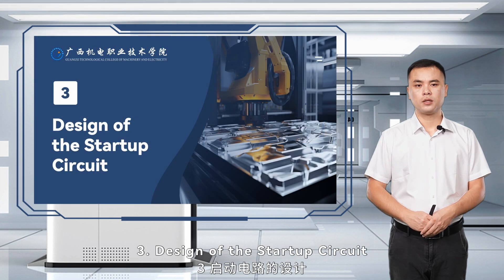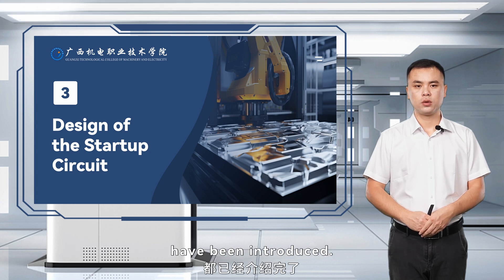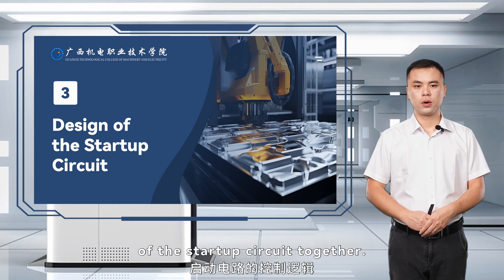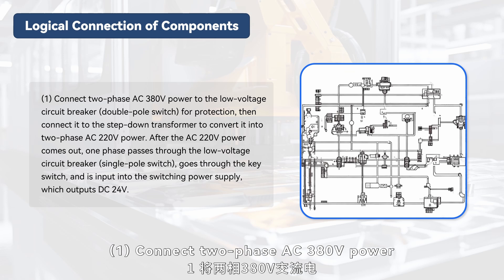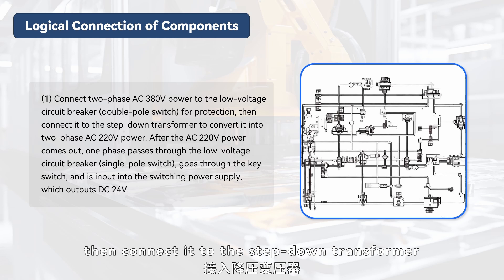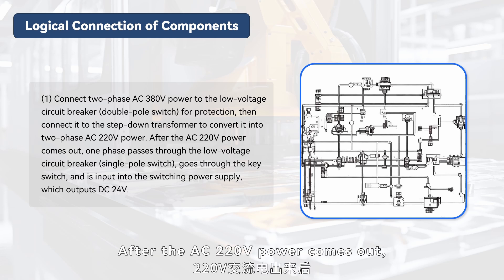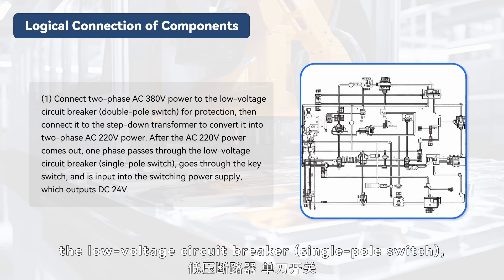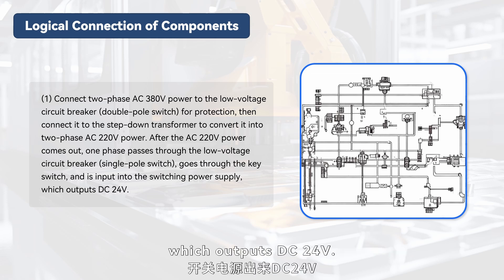Design of the Startup Circuit. All the components needed for the CNC machine tool system startup circuit have been introduced. According to the task requirements, let's review the control logic of the startup circuit. Step 1: Connect two-phase AC 380V power to the low-voltage circuit breaker (double-pole switch) for protection, then connect it to the step-down transformer to convert it into two-phase AC 220V power. After the AC 220V power comes out, one phase passes through the low-voltage circuit breaker (single-pole switch), goes through the key switch, and is input into the switching power supply, which outputs DC 24V.